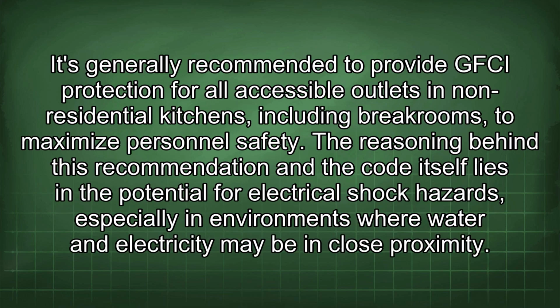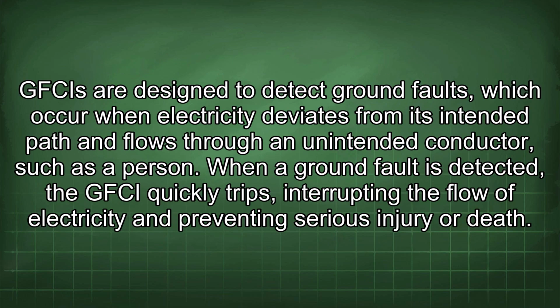requirements. It's generally recommended to provide GFCI protection for all accessible outlets in non-residential kitchens, including breakrooms, to maximize personnel safety. The reasoning behind this recommendation and the code itself lies in the potential for electrical shock hazards, especially in environments where water and electricity may be in close proximity. GFCIs are designed to detect ground faults, which occur when electricity deviates from its intended path and flows through an unintended conductor, such as a person.